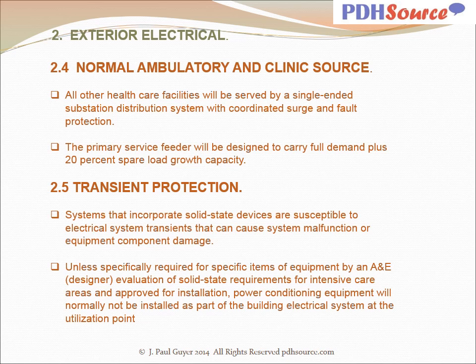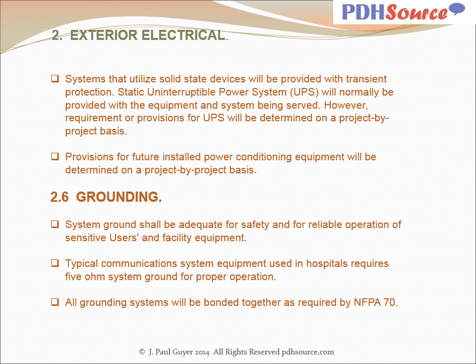With regard to transient protection, systems that incorporate solid-state devices are susceptible to electrical system transients that can cause system malfunction or equipment component damage. Unless specifically required for specific items of equipment by an AE evaluation of solid-state requirements for intensive care areas and approved for installation, power conditioning equipment will normally not be installed as part of the building electrical system at the utilization point. Systems that utilize solid-state devices will be provided with transient protection. Static Uninterruptible Power System, UPS, will normally be provided with the equipment and system being served. However, requirement or provisions for UPS will be determined on a project-by-project basis. Provisions for future installed power conditioning equipment will be determined on a project-by-project basis.